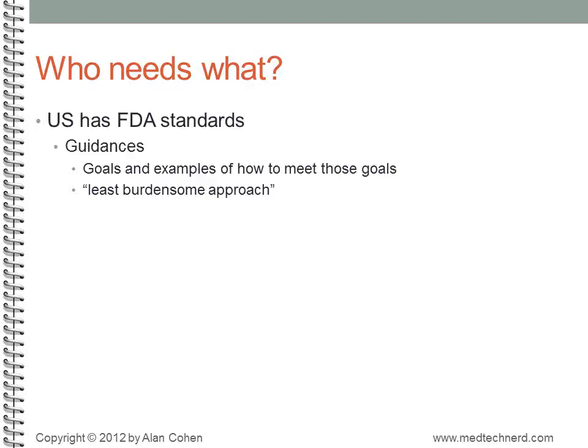These tend to communicate goals, give examples, and make suggestions about how to meet those goals, but they generally don't mandate the specifics of how the goals are met. Rather, they call on the manufacturer to determine what FDA calls the least burdensome approach to meeting these higher-level goals.